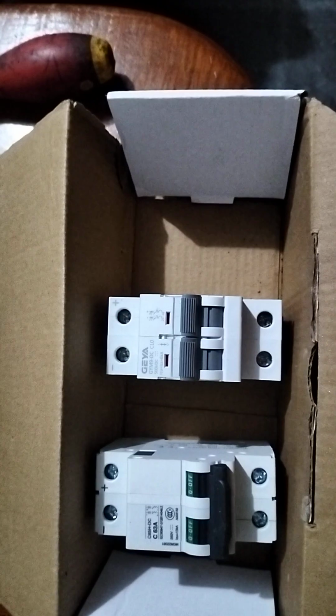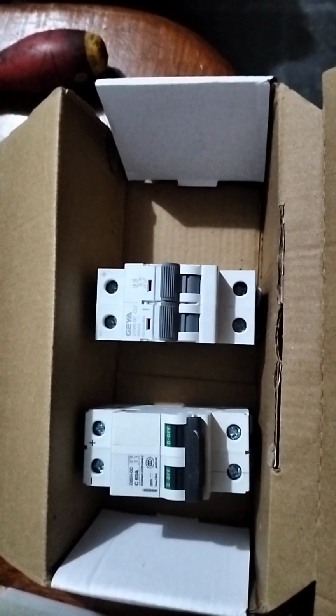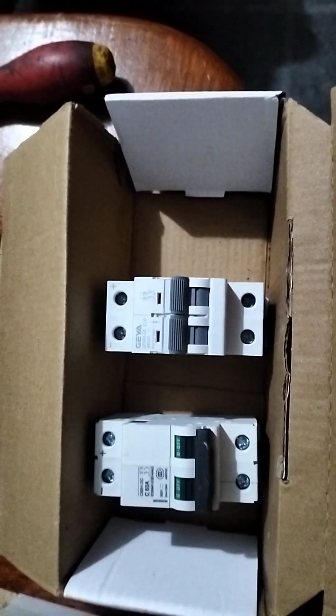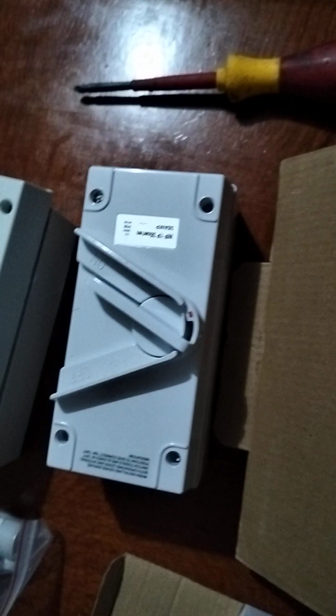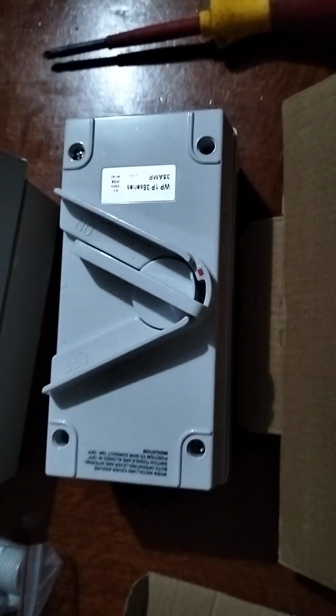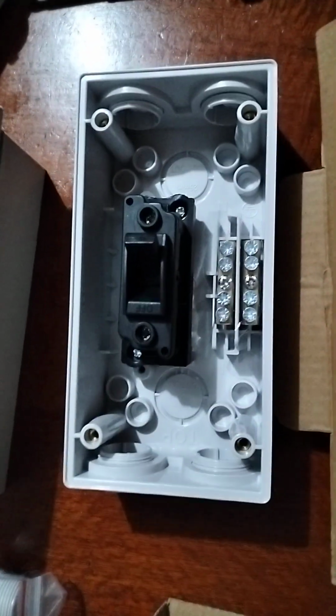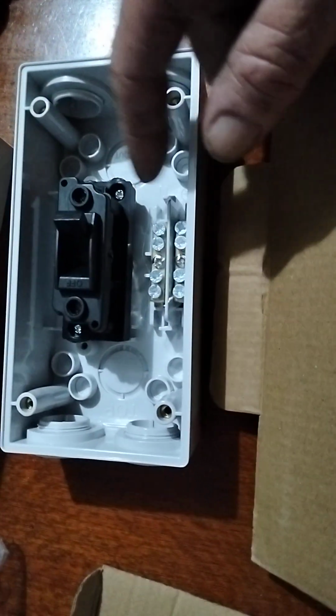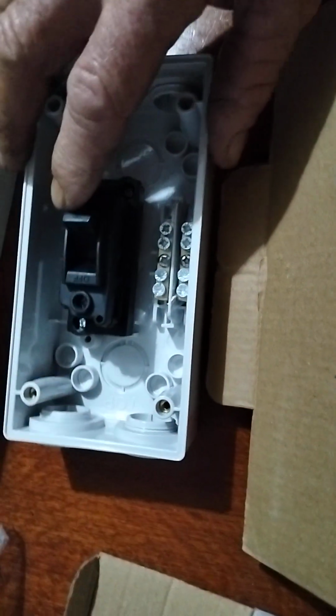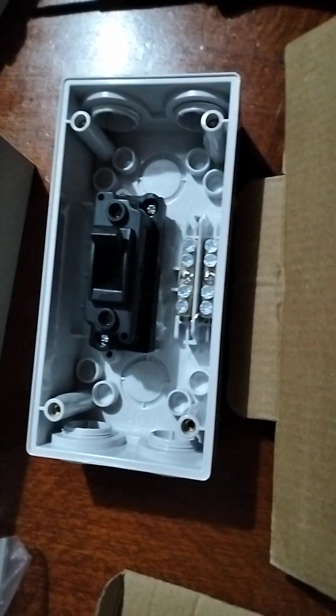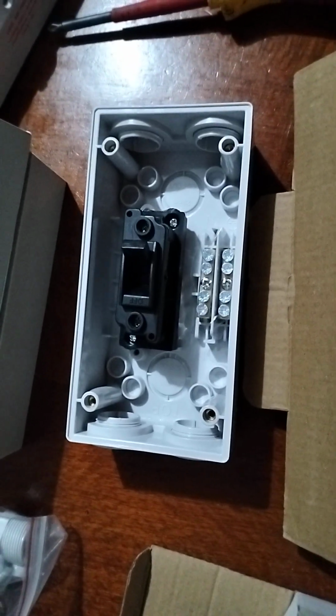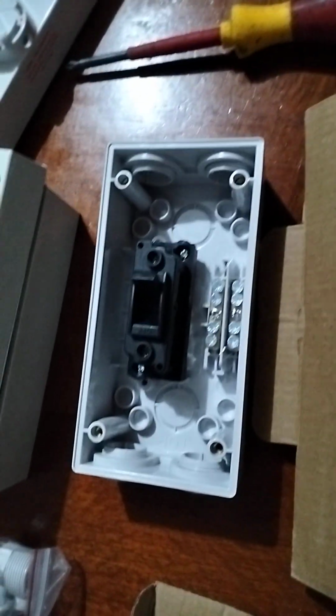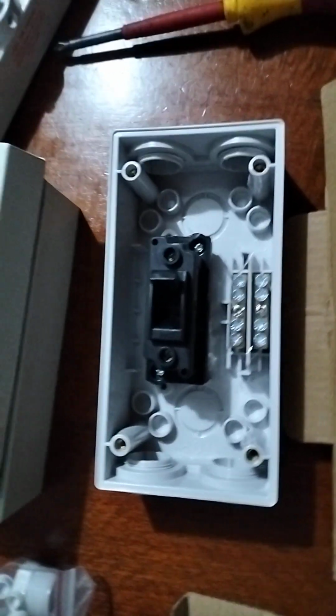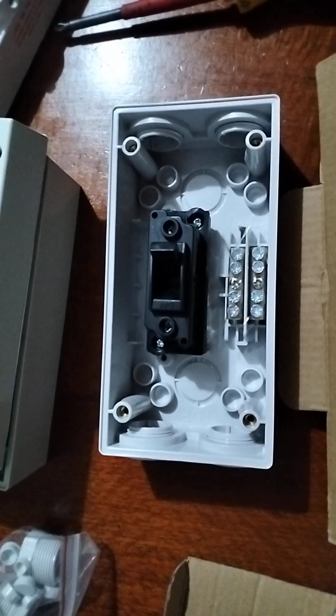It's 10 amps, and from there we'll move on to the AC isolators, especially if you're running a generator or you've got grid but you're mixing your grid with your solar power. We use this isolator here. This is a single pole and you switch the active. One of these is a neutral, the one closest to the switch, and the other one's the earth, but you only need to switch the active conductor because your neutral is tied to earth and it's part of your protective earthing system. Well, they're tied together at the neutral bar, so you only need to switch the active or line, live or hot as it's called in other countries.